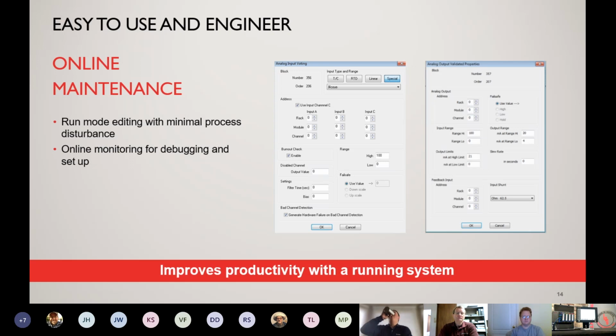The programming software also acts as a diagnostic or troubleshooting software. In the programming, it gives you the capability to go into the blocks in an online mode and actually visually see on that block the inputs, the outputs, the live process variable, the set point values, even the discrete values that are going on with the process while the process is running. This is a very, very powerful tool because you get a combination of both troubleshooting and programming in the same tool, and it allows for a very nice troubleshooting tool if you needed it out in the field.